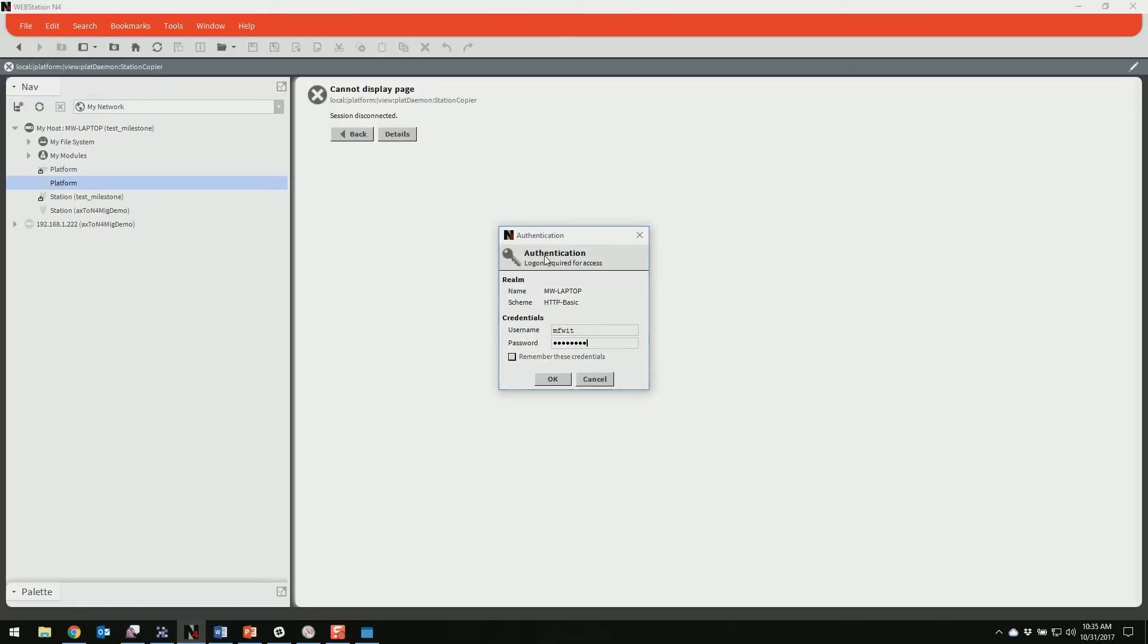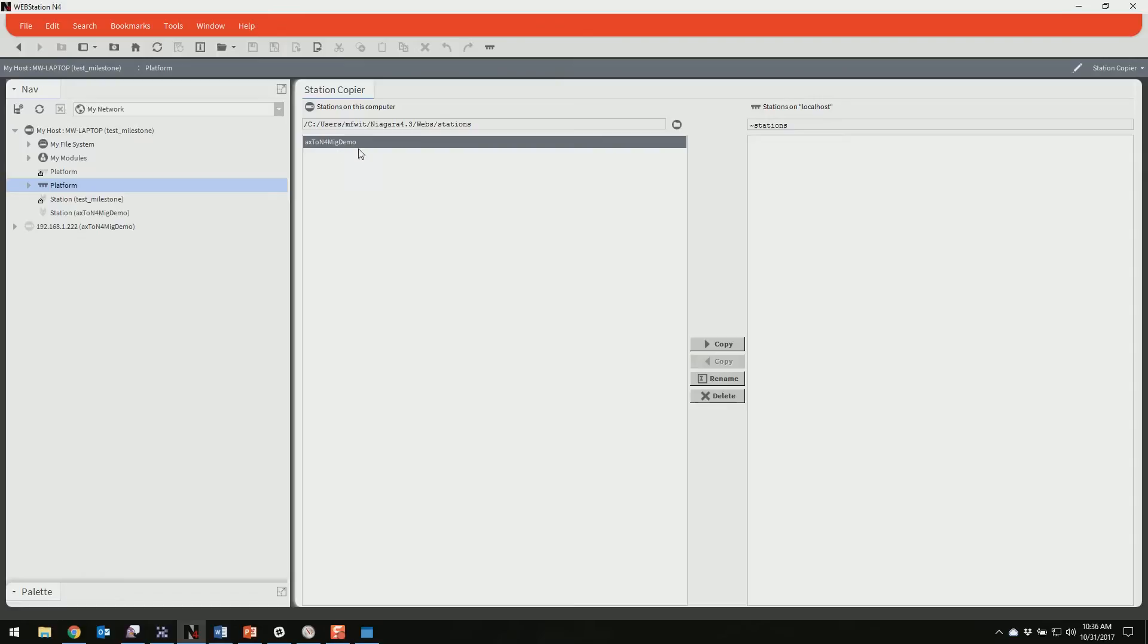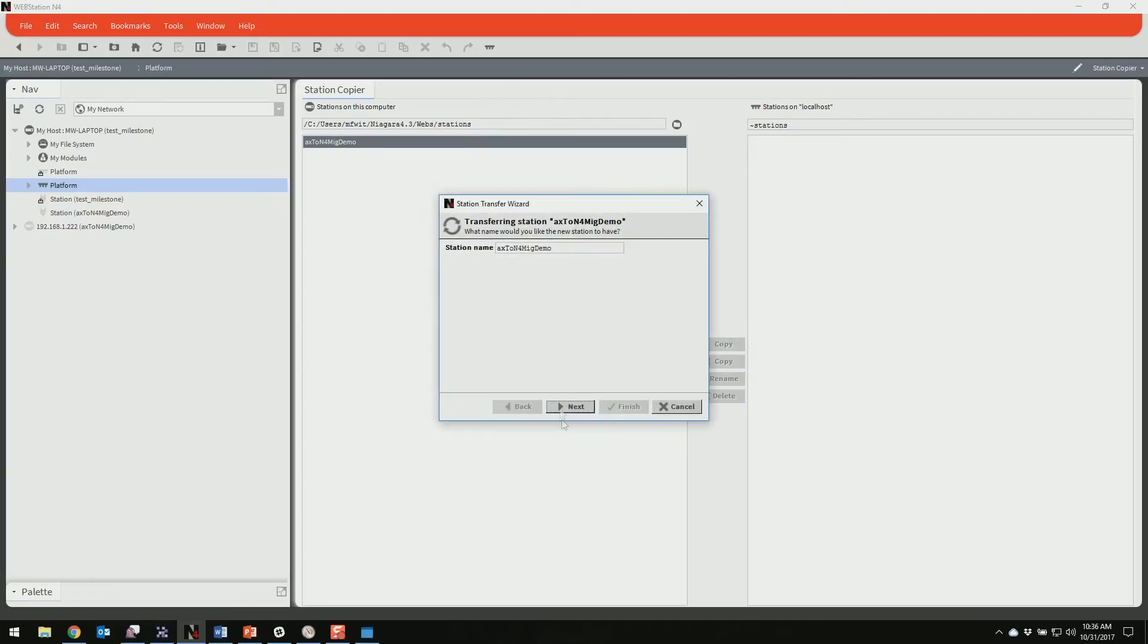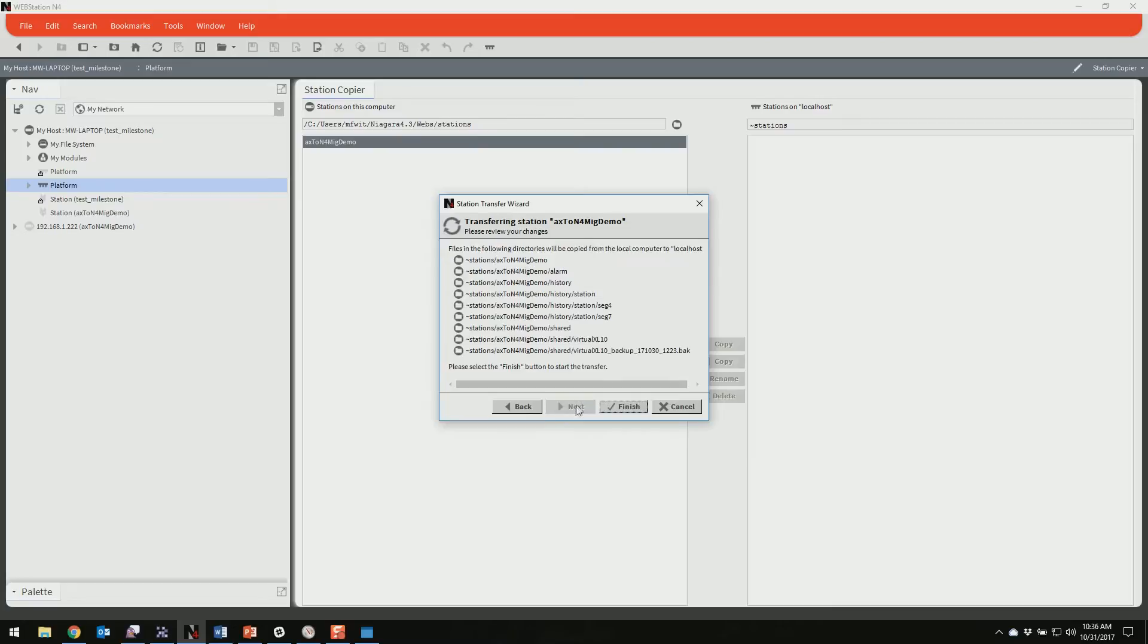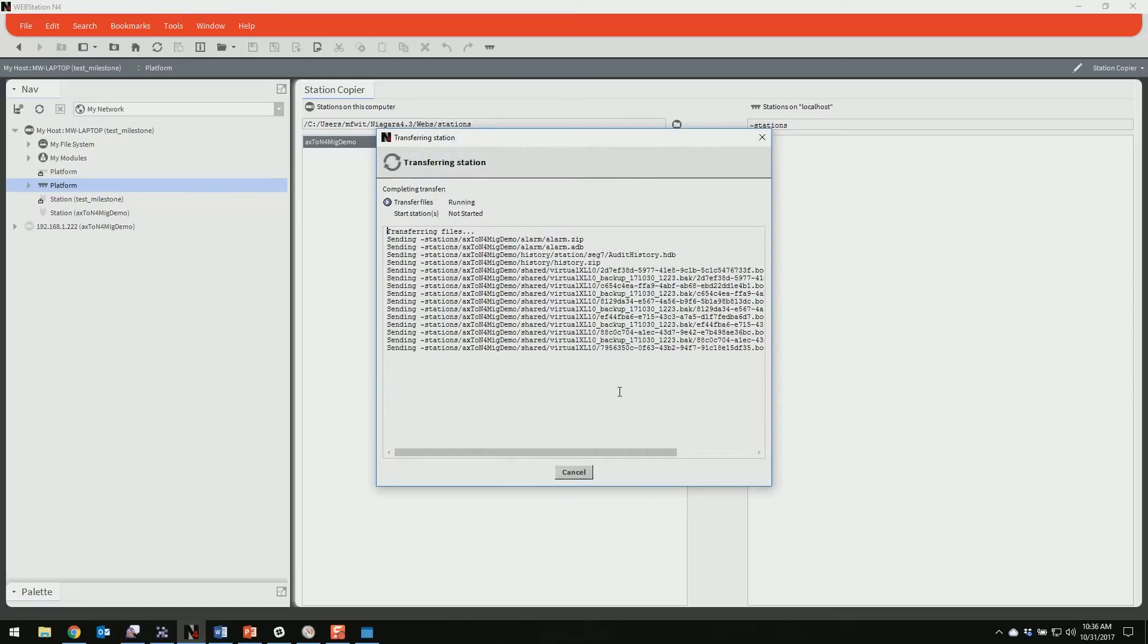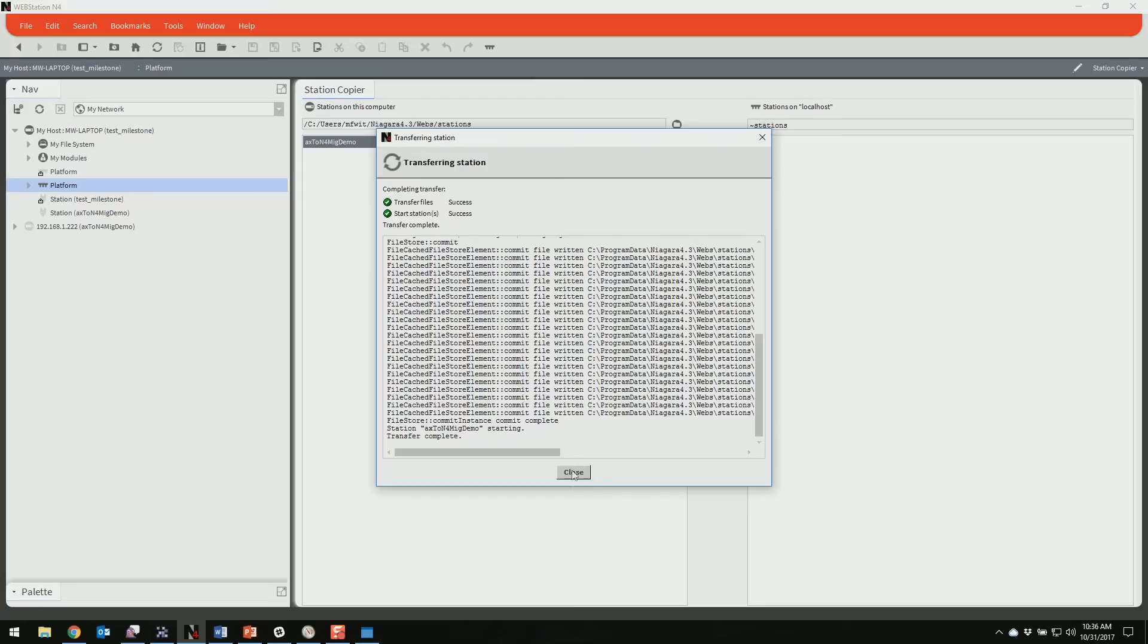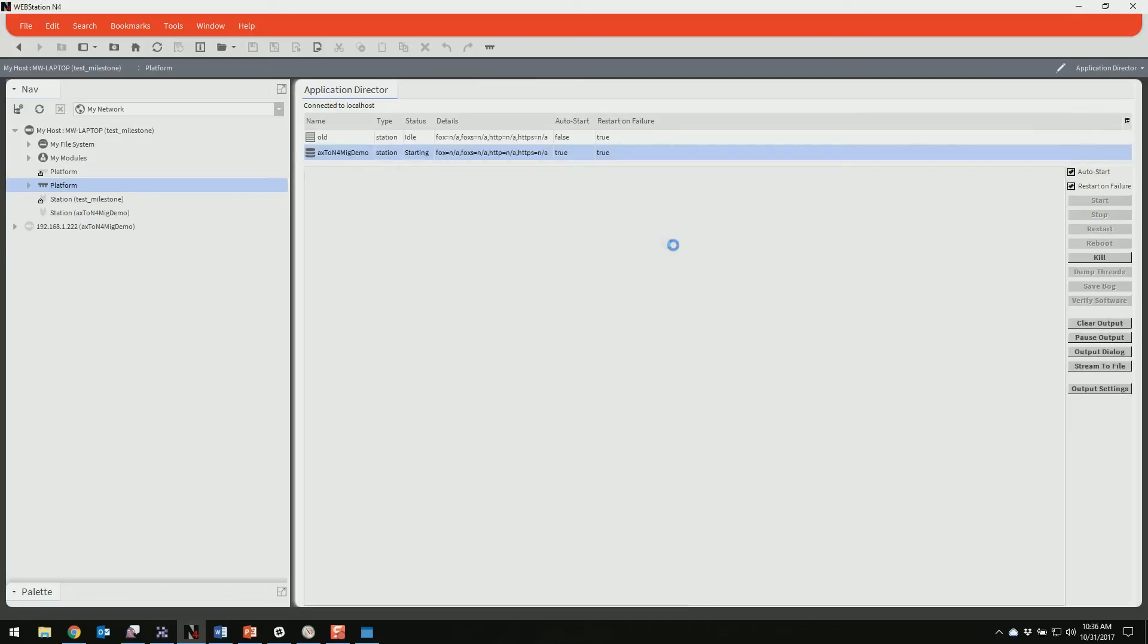And I'm going to log into the platform and we're going to go to the station copier. Now you'll see I have the station here on the left side. This was put here automatically by the migration utility, and the right side is empty. Now you don't need to do this step, but it's always a good thing to make sure that it runs properly on your machine before you spend the time and effort to put it onto a Jace. It's easier to make the mistake here than it is to make it on the Jace. So I'm going to copy it to the right hand side. And it's going to tell me that it has history and alarm data, which is good. And we're going to finish. And it's all done.